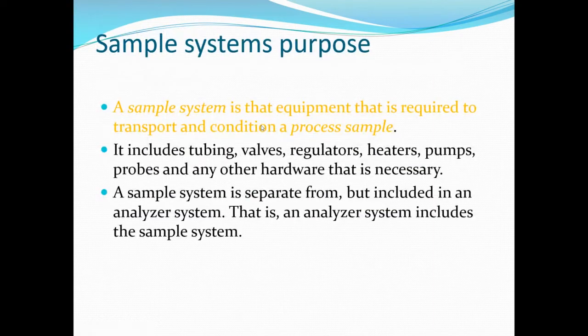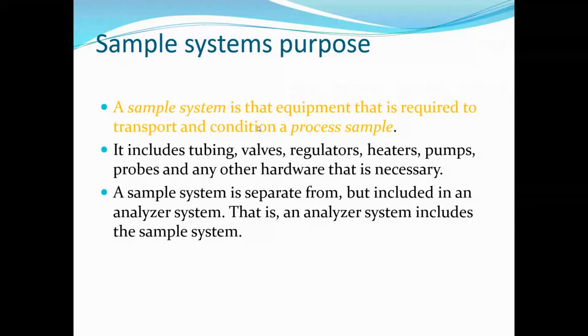What is the purpose of a sample handling system? It's the equipment required to transport and condition a process sample — not only getting it from the process to the analyzer, but also conditioning the process sample to make it acceptable for the analyzer. It includes all the tubing, valves, regulators, heaters, pumps, probes, and any other hardware that may be necessary. The sample handling system is separate from but included in an analyzer system.